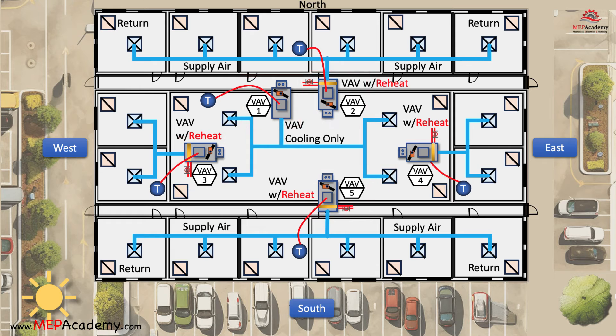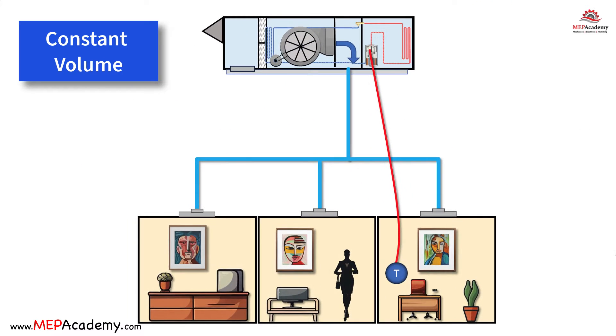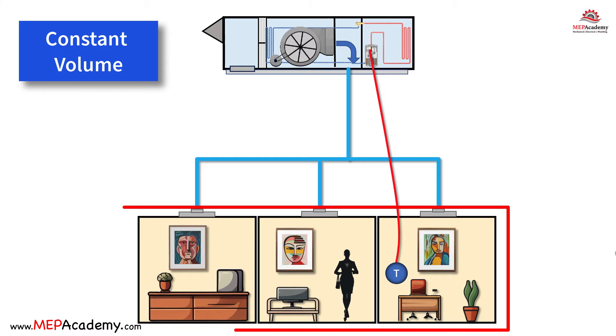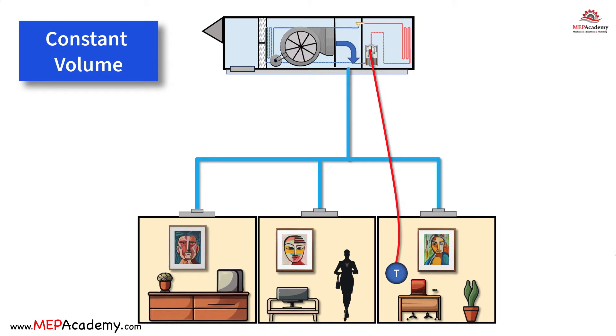As you can see in this diagram, each room has its own controller and can determine whether they want heating or cooling. Constant volume systems have limitations when it comes to zoning. In constant volume systems, the same airflow is delivered to all zones simultaneously. This lack of individual control can lead to variations in temperature and comfort levels, and these systems struggle to adapt to changes in occupancy and temperature requirements within different zones.